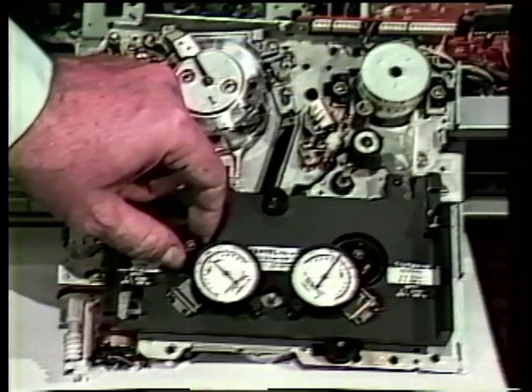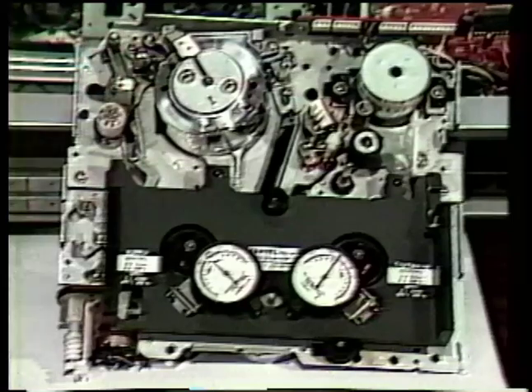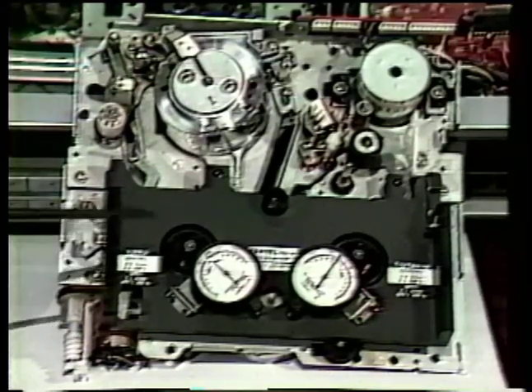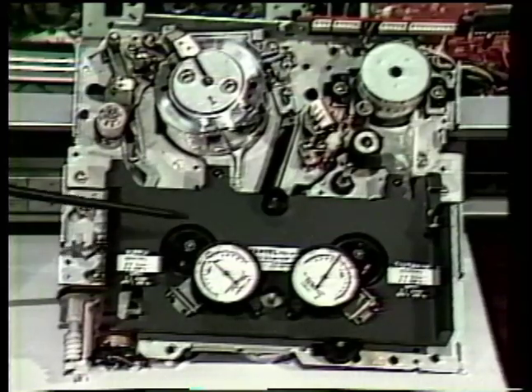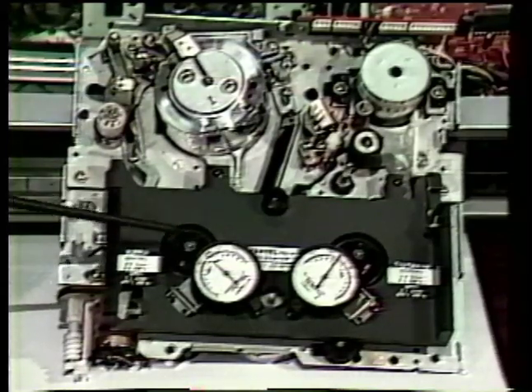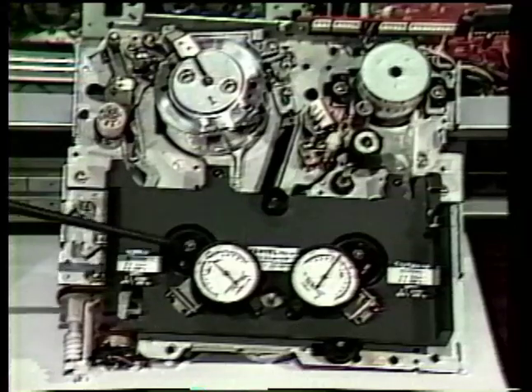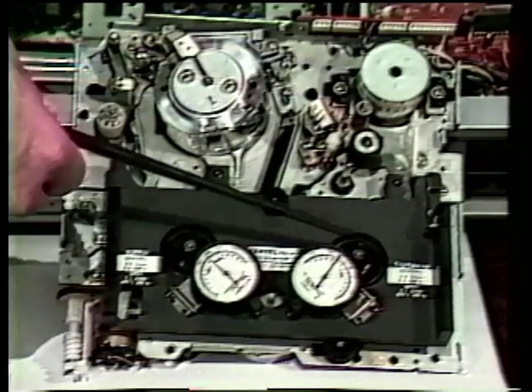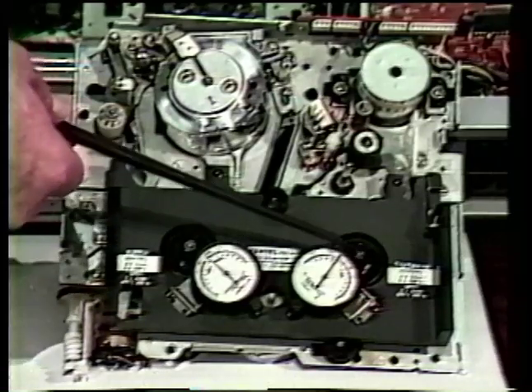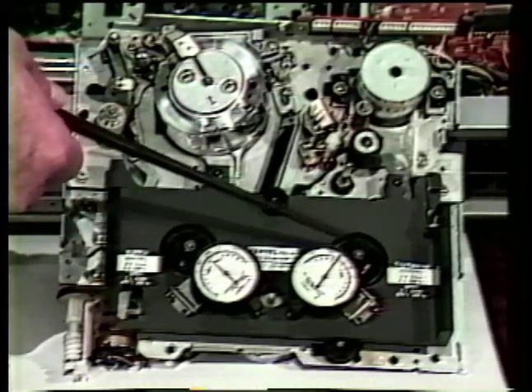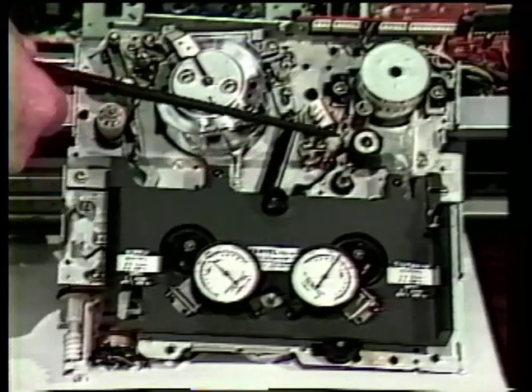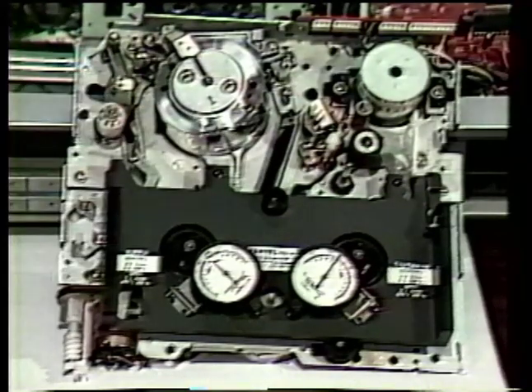So if there's only 1 or 2 thousandths of an inch, just a small amount down here, you can actually get a binding problem in the machine after the machine has been turned on for a while and had a chance to turn enough that it's actually heated through frictional drag of the spindle on the shaft, and actually start to get either a holdback tension problem if it's on this spindle or a take-up tension problem if it's on this spindle. What it would mean if this binds up, the tape starts spewing out, can get wrapped around the pinch roller and capstan, and of course cause a lot of tape damage at that point.